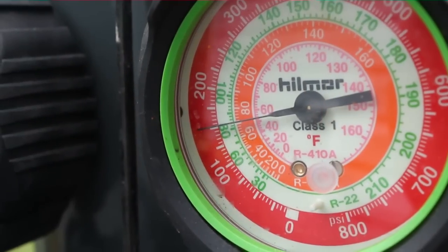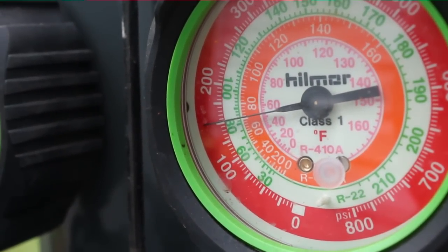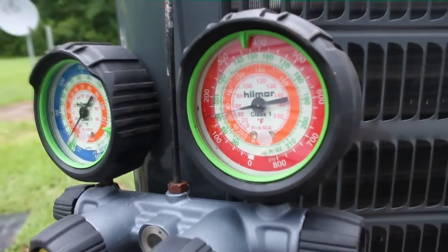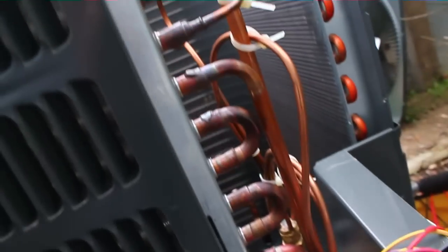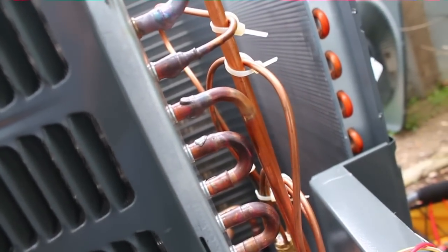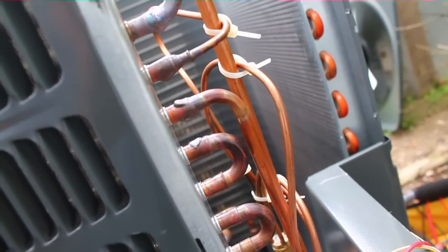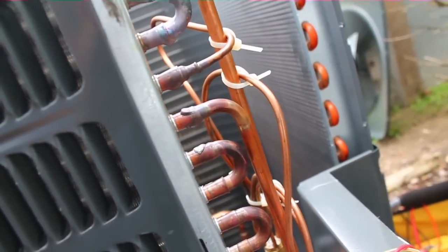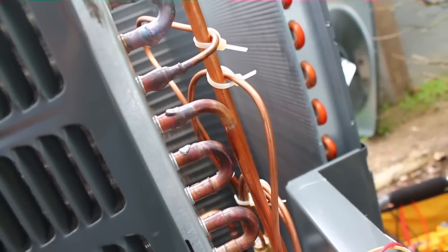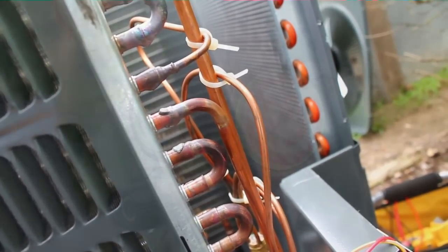We have nitrogen pressure on the heat pump right now. 150 pounds, a little bit over 150 pounds. So we will let it sit here for a while, make sure our joint is good, and then we'll test the rest of the system, button things back up because there's no power yet here at the house, and come back whenever they turn the power on to charge everything up.